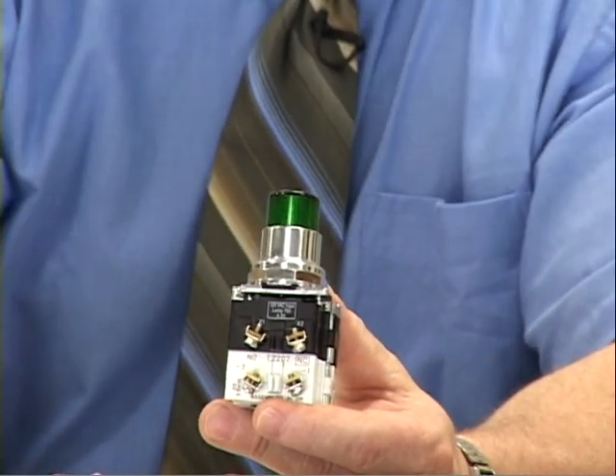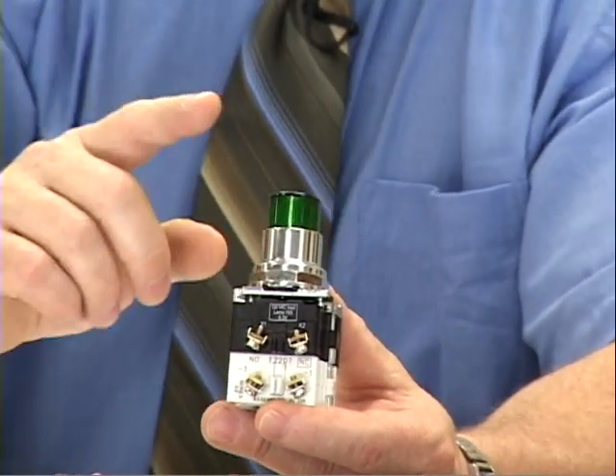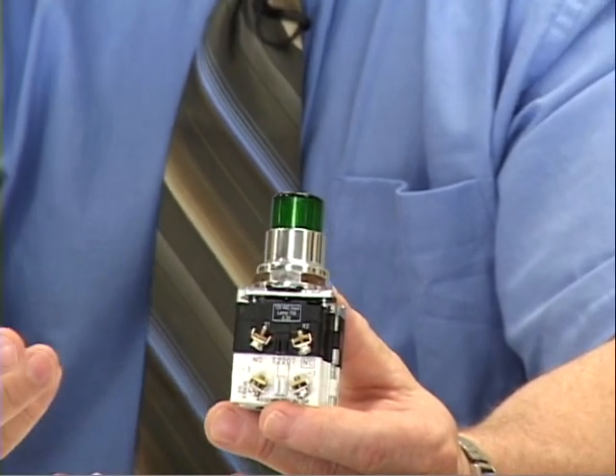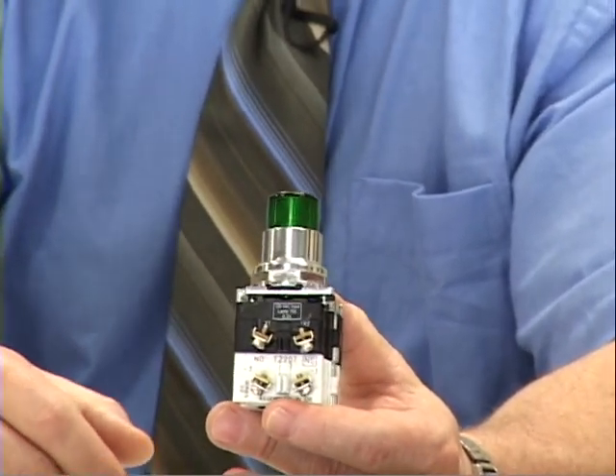If it shorts or it burns out, the filament in there is likely to short circuit and really raise your current. Hold on. You're saying you've got a 120 volt circuit, you've got a light bulb, there's a short circuit, and we are on a control transformer, right? Or you're on a programmable controller in your particular case, right? Yes. So when the bulb burns out, it short circuits, and now it draws a lot more current than it would have with the element being highly resistive. What's the effect of that? Well, since we use solid state outputs that are fused at 2 amps, you'll blow the fuse. Oh, right. And that's not a desirable effect.